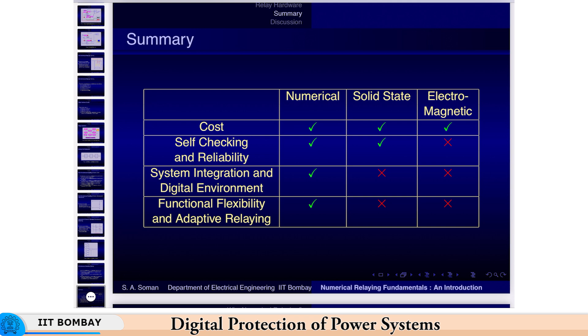Integration and functional flexibility is not just getting values from other relays and then changing the settings. It could also mean that with the proper inputs, the relay can be made to function as another device also. An overcurrent relay, if you could give voltage inputs from the substation LAN or arrange for VT inputs, you could also have it function as a distance relay. So you have functional flexibility also. This will be more and more apparent in the coming years when standards like IEC 61850 get implemented. So functional flexibility and adaptability will not be available with the other two relays, only with numerical relays.